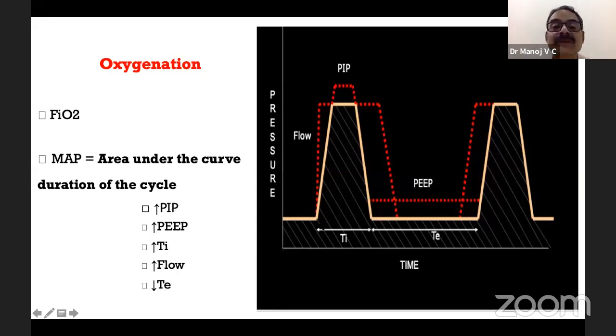So, let's define what a mean airway pressure is. Mean airway pressure is the area under this pressure curve from when the valve closes to the next time the valve closes, which means one full cycle: the valve closes, the valve opens, and then again the valve closes. The pressure generated over this period, the area under this curve, is your mean airway pressure. That's a simplified version. So if you want to increase this area, you can do many things. If you increase the PIP, you will increase the mean airway pressure and oxygenation.